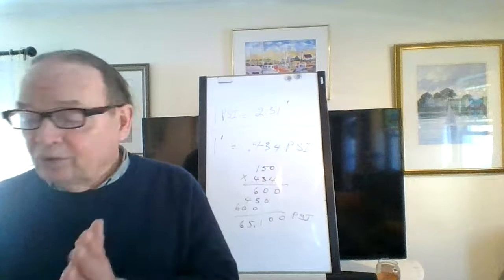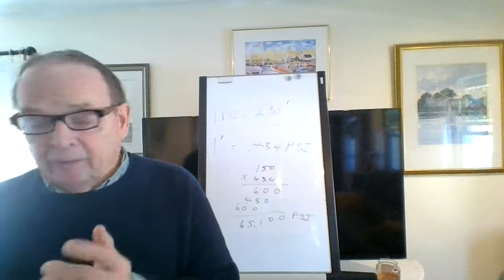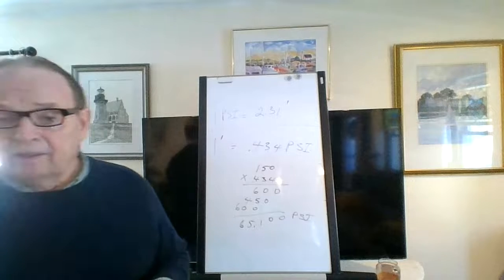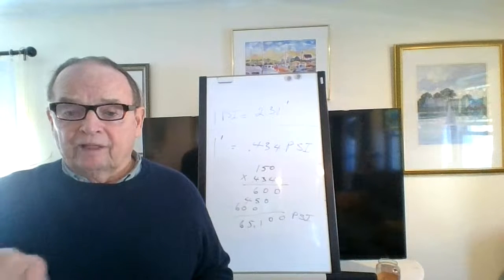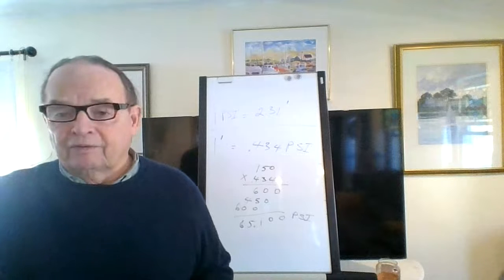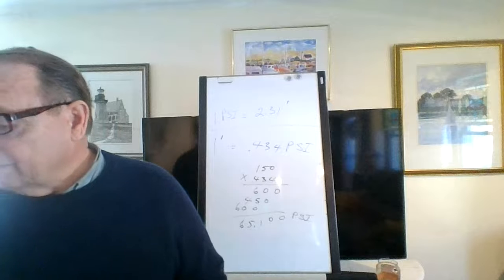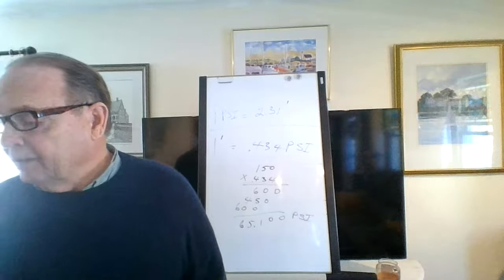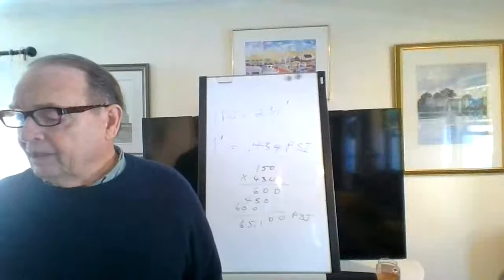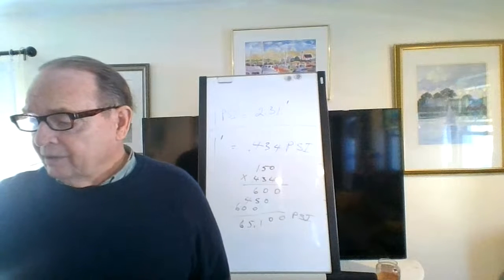Now those of you not familiar with water hammer, when you've got pressure up to 80 pounds or higher, and you've got a ball valve, right? How long does it take to turn the ball valve? A quarter of a second, on, off. And what happens is the water is surging. They give a pretty good explanation, a pretty good diagram here on page 107. Take a look at it. They've got the handle of some kind of ball valve, and you turn it sideways, and it shuts off.